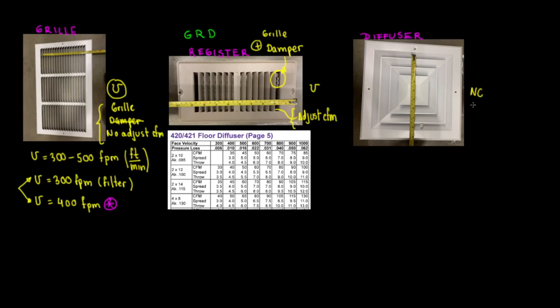For diffusers, the noise criteria depends on the application and the manufacturer. Diffusers are very useful for ceiling tiles and fit well for commercial applications — typically 24x24 or 12x12 sizes. The noise criteria should be below 25 NC, though it can go to 30 or 35 depending on the application, such as hospitals, schools, or restaurants.